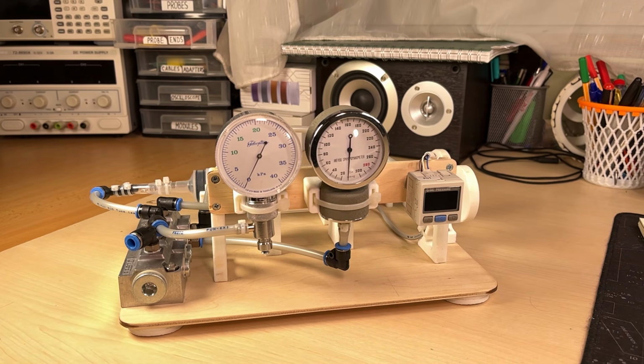I'll show you now the computer screen with the table where I have all the recorded data. You can see the whole table here. And in the end, just using the least mean square method, I estimated this line here. So we are expecting a linear response to the pressure, and that's what we got. And using these parameters here, we can convert the ADC values into actual pressure measurements. So that sums up the calibration process. It's a bit tedious, but it turned out pretty good in the end.